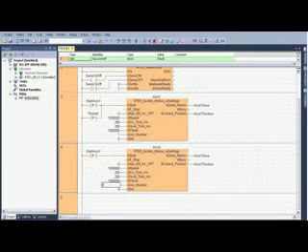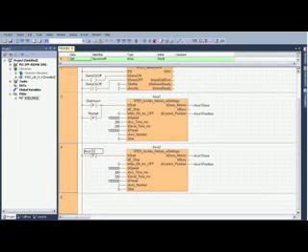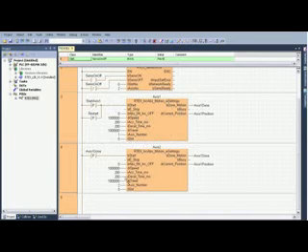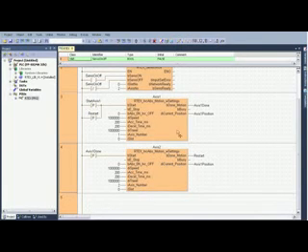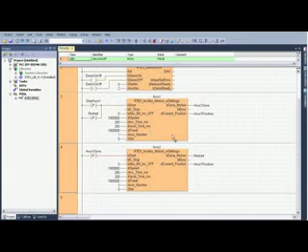And I want this to start when the first axis is done completing its rotation. So I'm going to change that to axis one done. So the logic is now the start axis is going to start this motion, it'll do about one turn. Once that's done it'll start this one which will do about one turn. Now for the done side here I'm going to put this as restart. I'll do that because I want this to alternate back and forth. So now once this is done with its rotation it'll activate the restart which then in turn activates the first axis motion again. So it'll just go back and forth indefinitely until I shut it off.